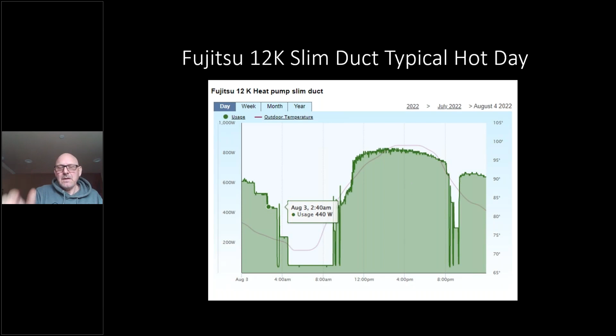So this system was designed for 12,000 BTUs. You can see our cooling load is really low. It's probably on its first or second low stage because it's a variable stage piece of equipment. The compressor can go up, it can go down, and it's just finding its sweet spot. It just has these long run times, and it's just loving life right here, working at its best efficiency. It's running from 600 to 800 watts that day. It was probably over 100 degrees that day.